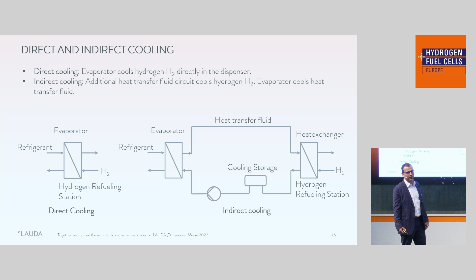What's the advantage? When you start the refueling process, you buffer the temperature using the buffer tank. So at first you use the minus 40 degrees, for example for a T40 fueling protocol, from the liquid in the storage tank, and then the cooling process circle works to cool down the recharged buffer tank for the next step.